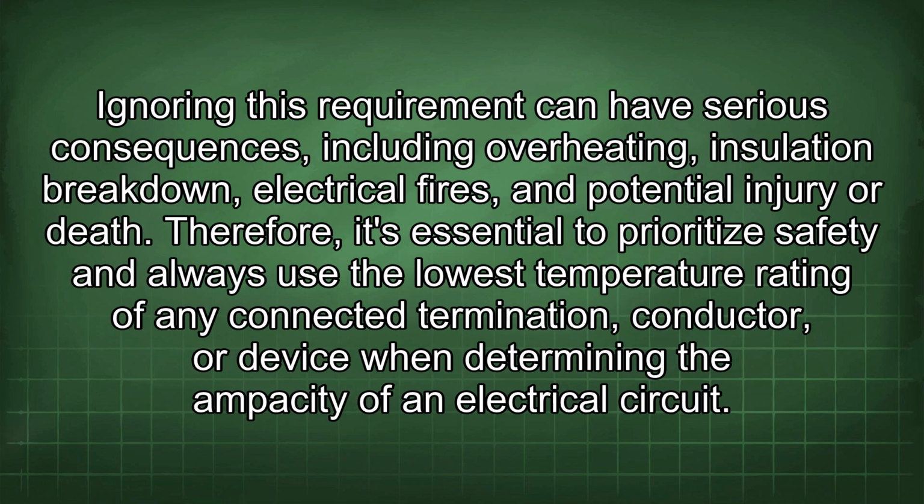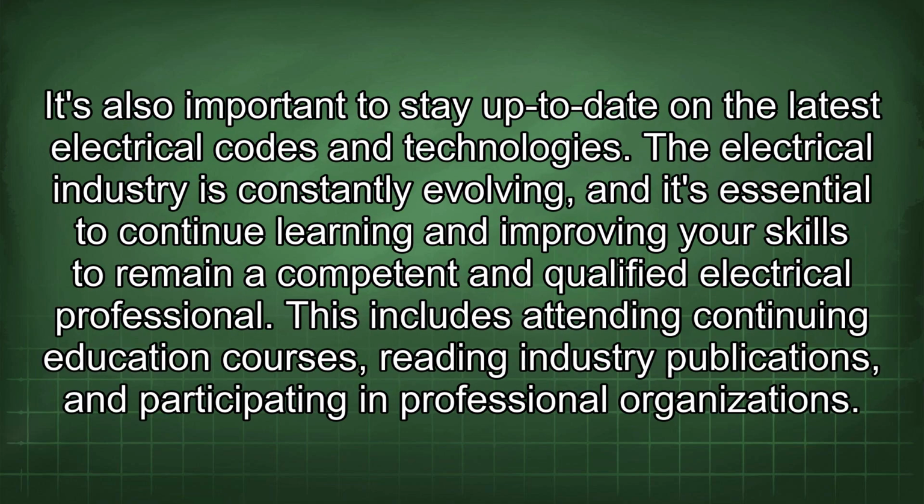Ignoring this requirement can have serious consequences, including overheating, insulation breakdown, electrical fires, and potential injury or death. Therefore, it's essential to prioritize safety and always use the lowest temperature rating of any connected termination, conductor, or device when determining the ampacity of an electrical circuit. It's also important to stay up to date on the latest electrical codes and technologies.